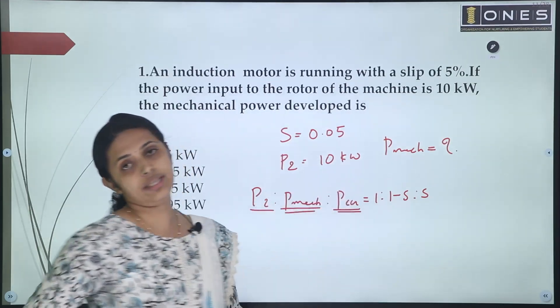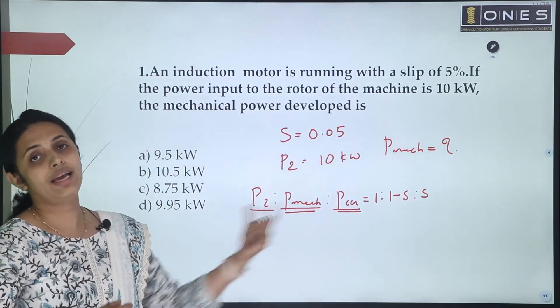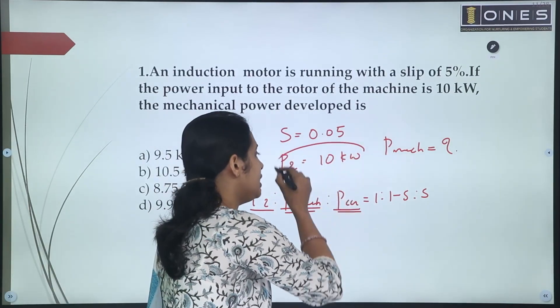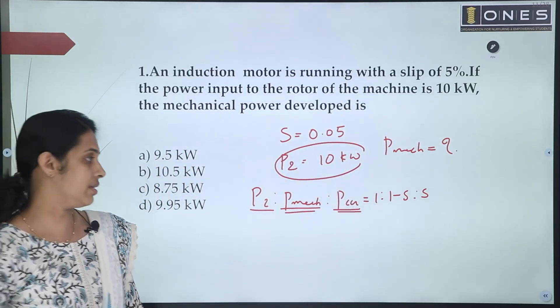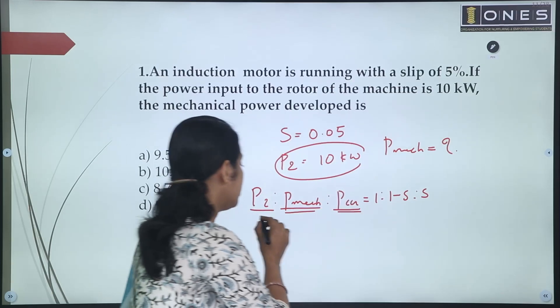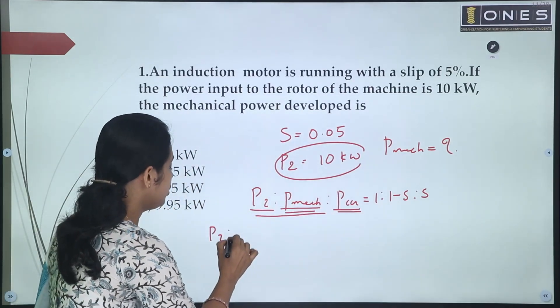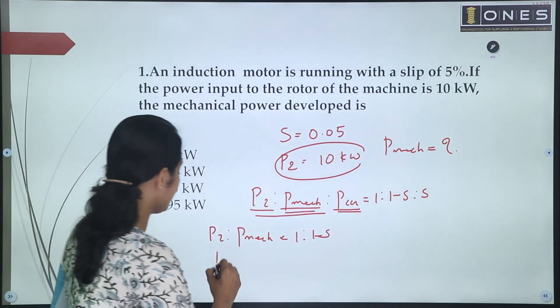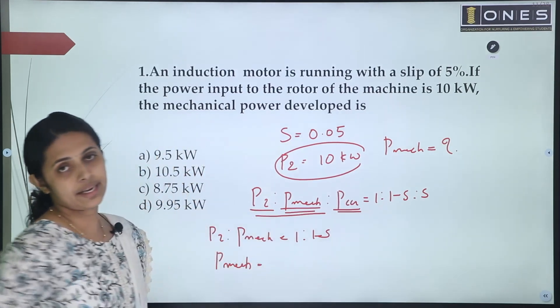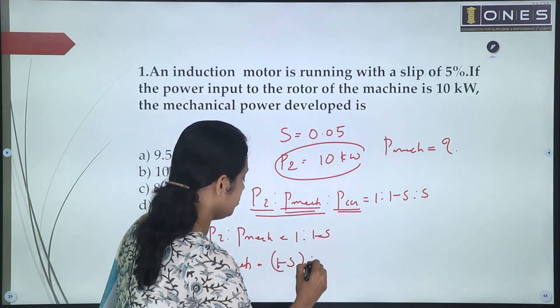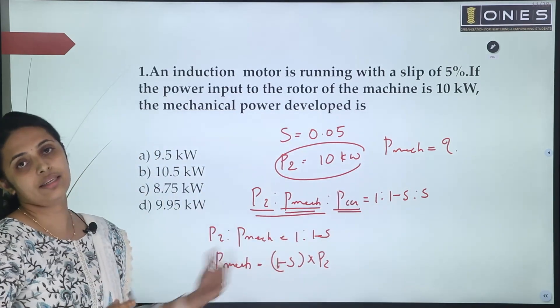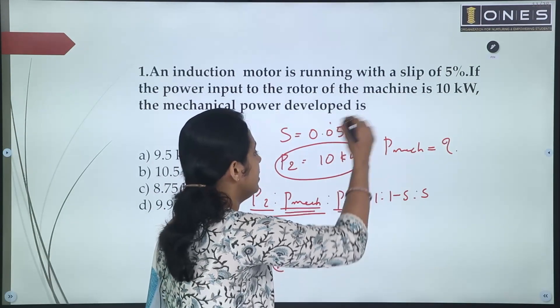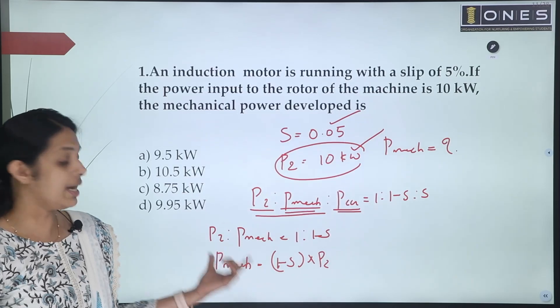Once we have a quantity, we calculate the others. P2 = 10kW. To find Pmec, we use the first two relationships: P2 : Pmec = 1 : (1 - S). So mechanical power developed = (1 - S) × P2 = (1 - 0.05) × 10kW = 0.95 × 10kW. That gives us the mechanical power developed.